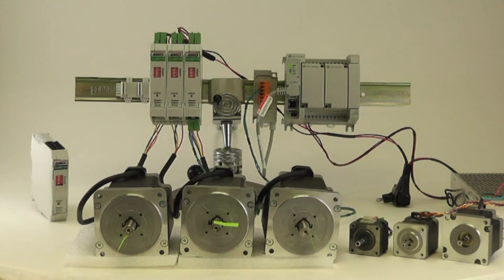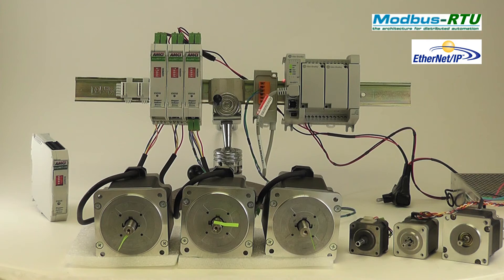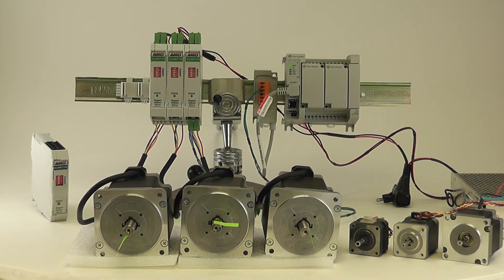Not only because it's network connected, but also because it communicates over the network to any PLC or PAC which supports to-date Ethernet IP or now, as you can see here, Modbus RTU. But also because it can be connected to stepper motors as small as a frame size 17, single stack, double stack, up to a NEMA size frame 23, all the way up to what you see here, which is a NEMA frame size 34.